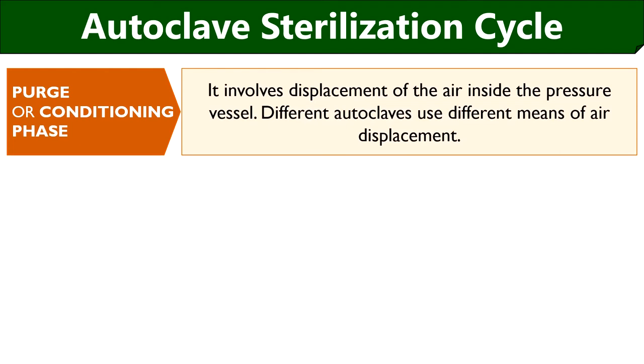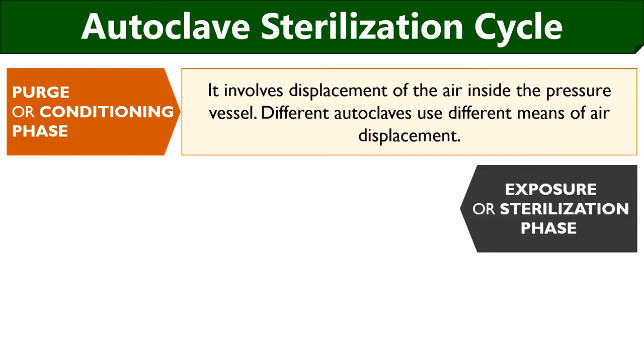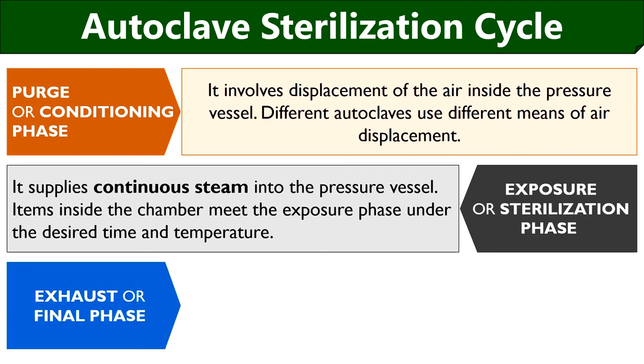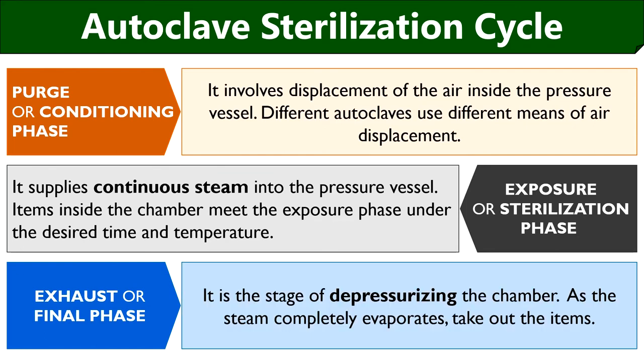Different autoclaves use pressure pulses, steam flushes, or a vacuum pump to displace the air. Then in the exposure or sterilization phase, we need to close the exhaust valve in order to supply continuous steam by switching on the heating element. This causes a rapid increase in temperature and pressure, after which the items placed within the pressure vessel meet the exposure phase. The exhaust phase is the final phase in which we open the exhaust valve to release steam out of the chamber — this is the stage of depressurizing the chamber. As the steam completely evaporates, the items can be taken out.